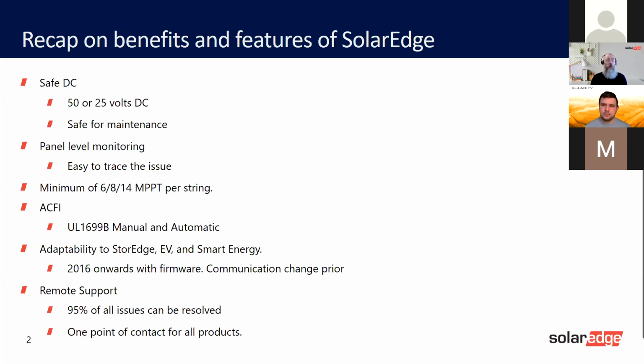Per string, and also it removes the current level from about 14 to 15 amps, which is in a normal string, to about 200 to 300 milliamps. So we have our arc fault circuit interrupter. This detects an arc, a parallel arc or a series arc, and then using the safe DC, we then turn off the optimizers. We stop the optimizers from passing current through, reducing the current to below 300 milliamps. This then reduces the arc, because an arc is a jump between two conductive pieces of equipment through air. So that reduces the current and therefore stops the arc.